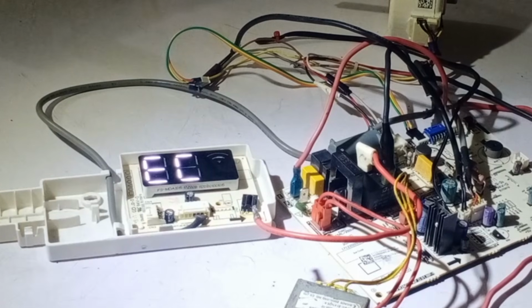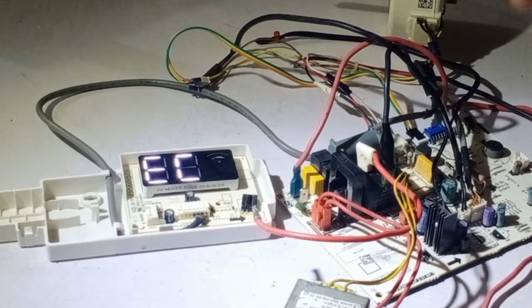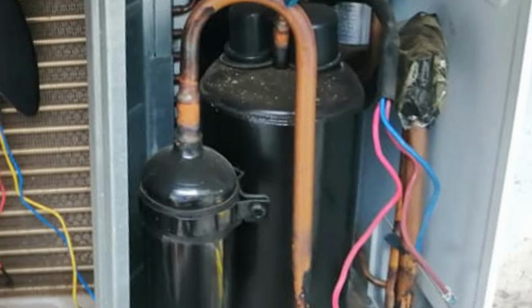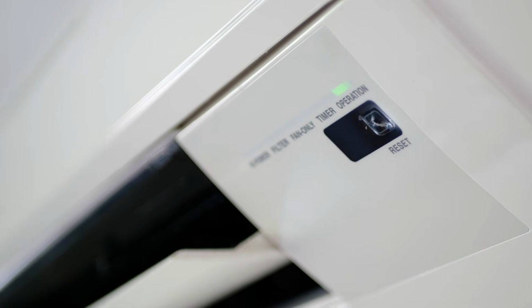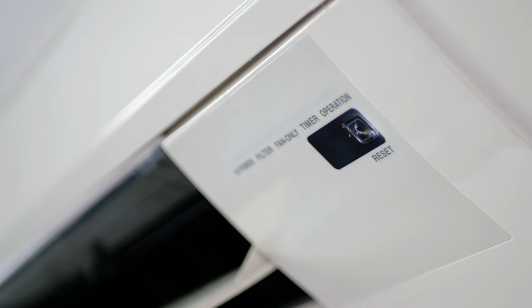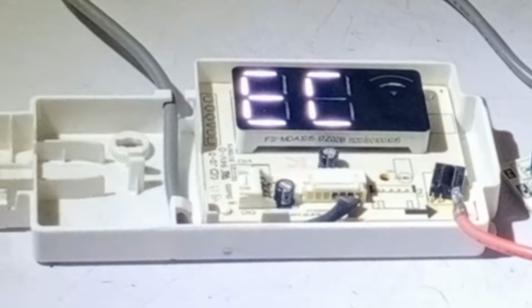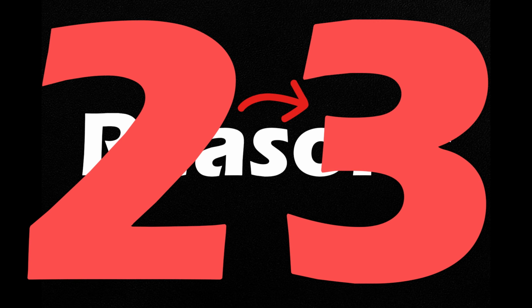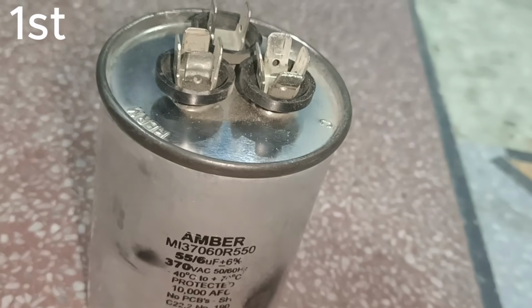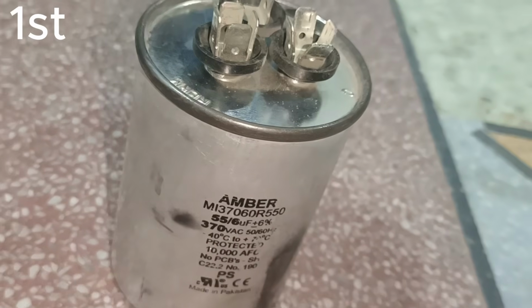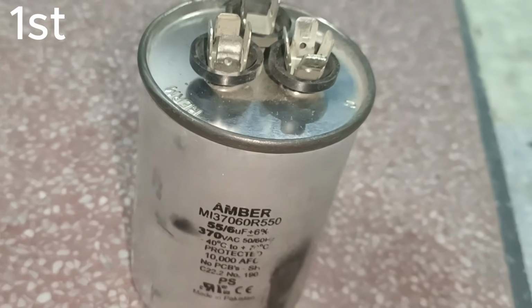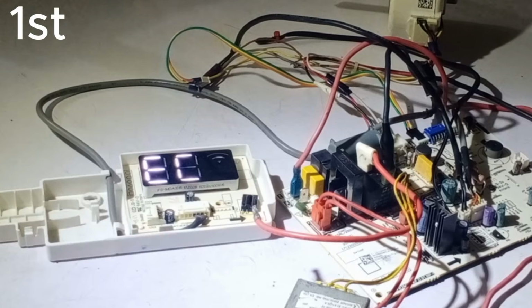Now, if I talk about the EC error code on the conventional mini split air conditioner, the first reason could be that the compressor may not start in your outdoor unit. The indoor unit has supplied power to it, but it is not starting. Then, the EC error code will be displayed. There could be 2 to 3 reasons that the compressor is not starting. The first is when the capacitor installed with the compressor is bad. The compressor will not start. The unit will start to show an EC error code on the unit.